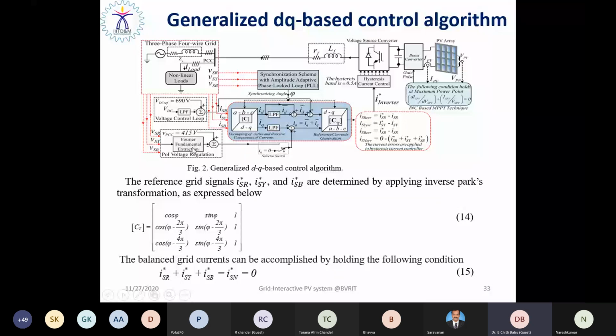In the meanwhile, we also sense the three-phase AC voltage. This is responsible for the reactive power control. So during balanced conditions, there is no need of any reactive power support, so IQ is basically zero. But whenever an unbalanced load is connected, there is a need of reactive power to improve the voltage profile. So IQ is responsible for the reactive power control, and ID is responsible for active power control, but both components are orthogonal with each other. Then the corresponding ID and IQ components are transformed into ABC, so that we are able to generate the reference current.